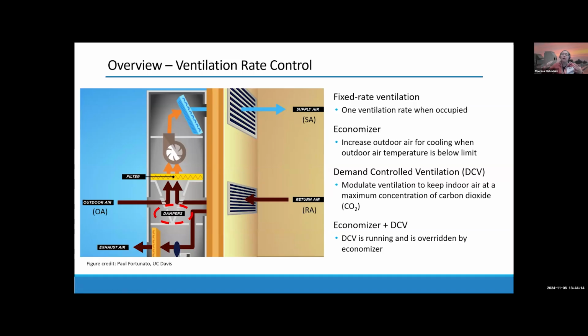We're creating carbon dioxide. The control system is working to maintain CO2 at a set point, and it attempts to adjust the damper accordingly to have like a steady state CO2 concentration. And then finally, we can combine economizer and DCV so that we're running DCV, and then when we need free cooling, the economizer will override the DCV and bring in 100% outside air.